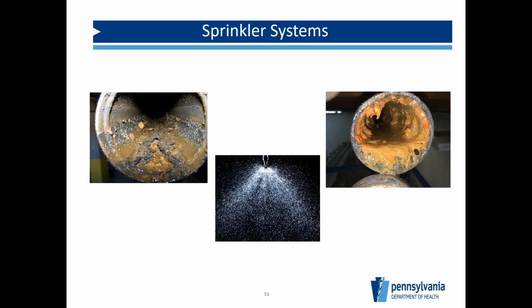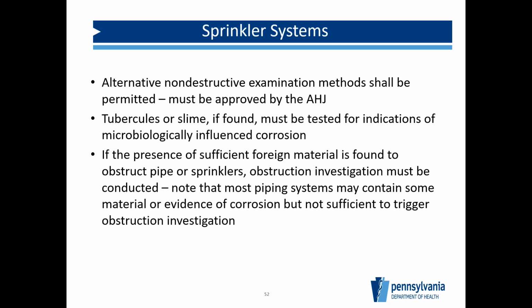But if anybody has been unlucky enough to see the sprinkler system go off, it's not shower water. It can be pretty dirty. So what you're looking for is you don't want to see the picture on the right, where we have all sorts of slime and material inside the sprinkler pipe, because then our sprinkler water is not going to come out properly. So if we do find materials, then you're going to get put on a program called obstruction investigation, and that's a little even more invasive.